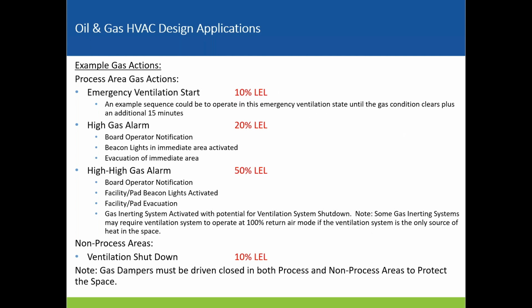Process area gas actions, emergency ventilation start. This is just an example of what you could do. Different operators will have different guidance on what they like to see. Say we hit a 10% LEL on a gas detection system, that can start our emergency ventilation rate on that larger unit we were looking at, until the gas condition clears plus an additional 15 minutes.